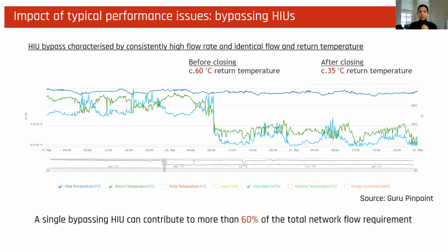As an example of the impact that this can have on network performance, on one of the investigated networks we identified one single bypassing HIU, which contributed to more than 60% of the total network flow requirement. This resulted in a significant increase in the network return temperature and drove heat loss and electricity requirements for the site. So by targeting maintenance into particularly poorly performing dwellings, that can have a significant effect on the overall network performance at relatively low cost with relatively little intervention.